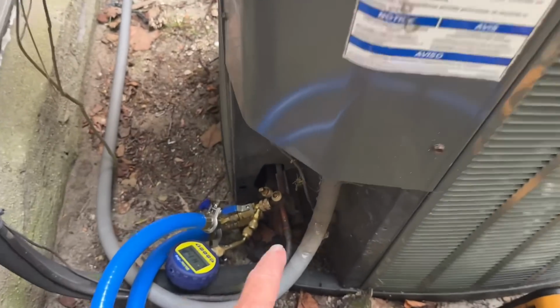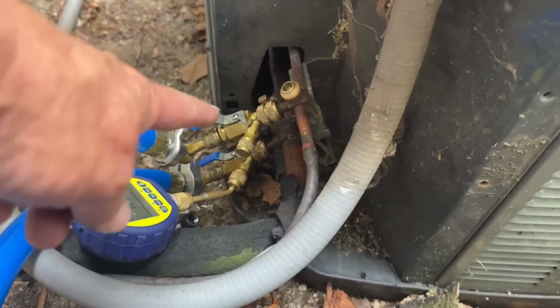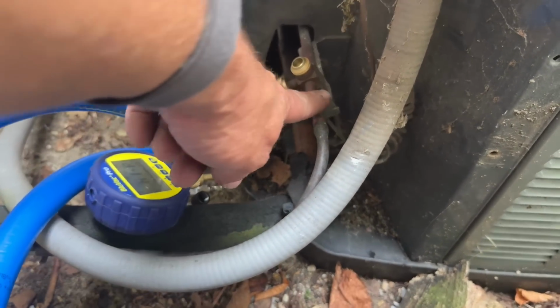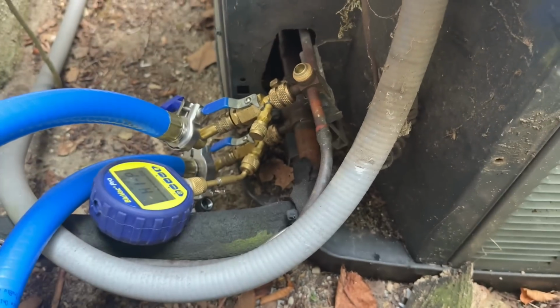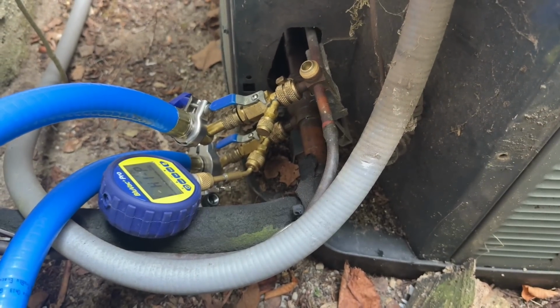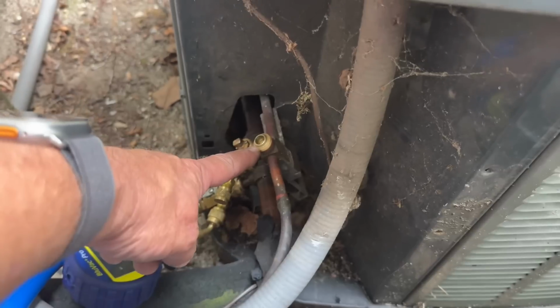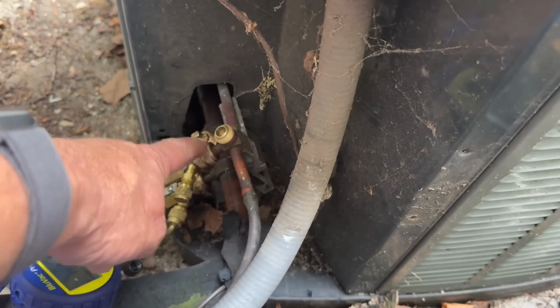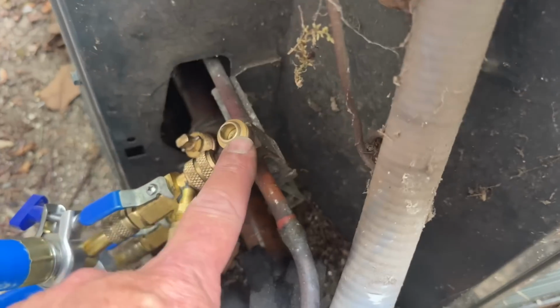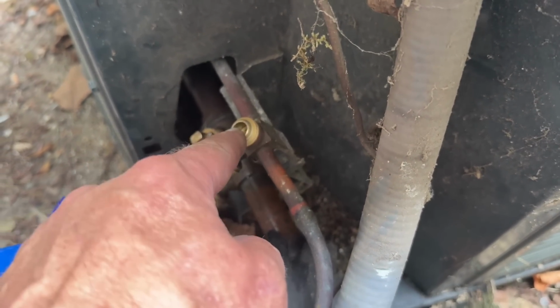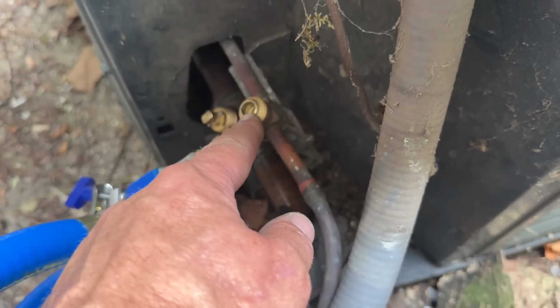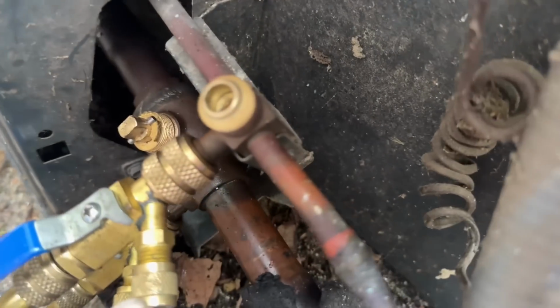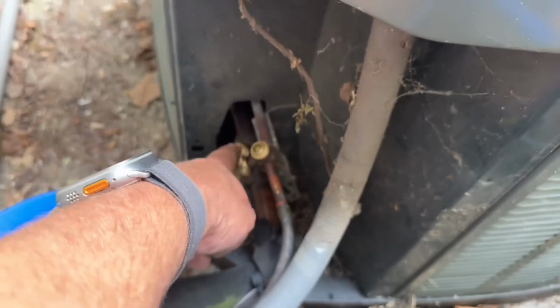We removed the two Schrader core valves on our high side and our low side. If you stick around, I am going to reinstall them when we're done vacuuming the system down. Okay? This is closed. That is closed. You can see that this one is one that you use an Allen key or a service wrench to close and then reopen. See how it's all seated fully down? And that's closed like a ball valve.